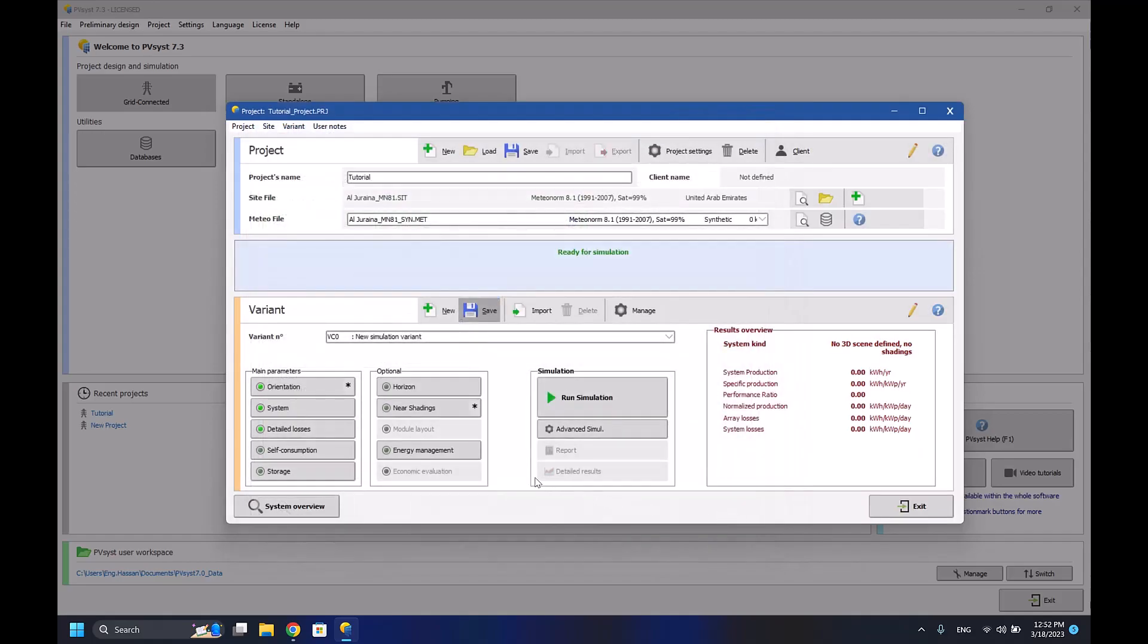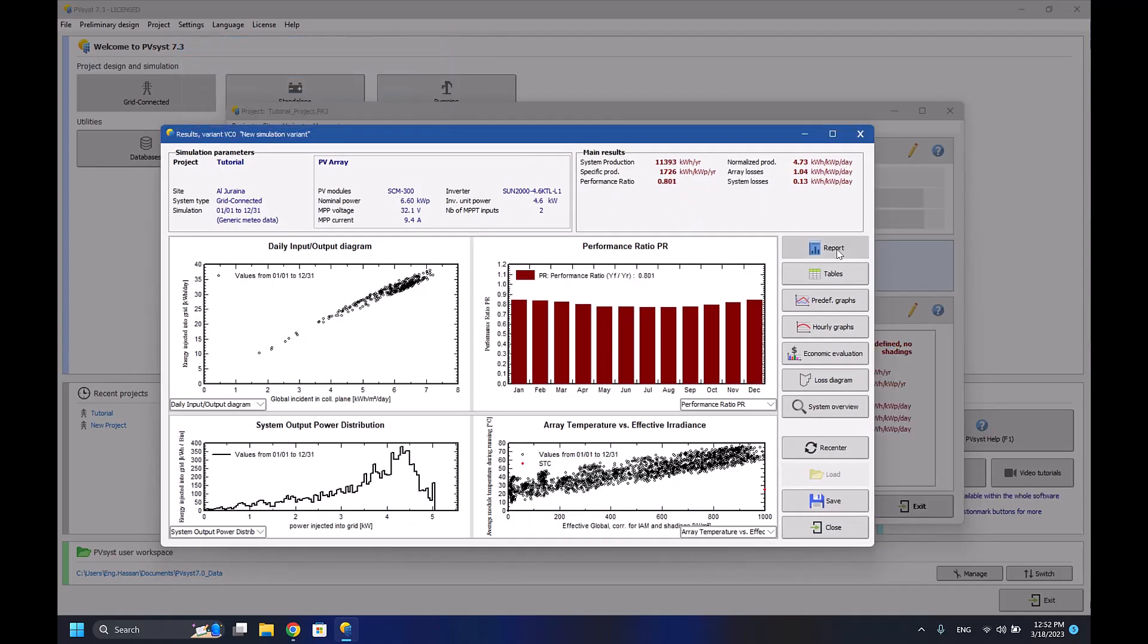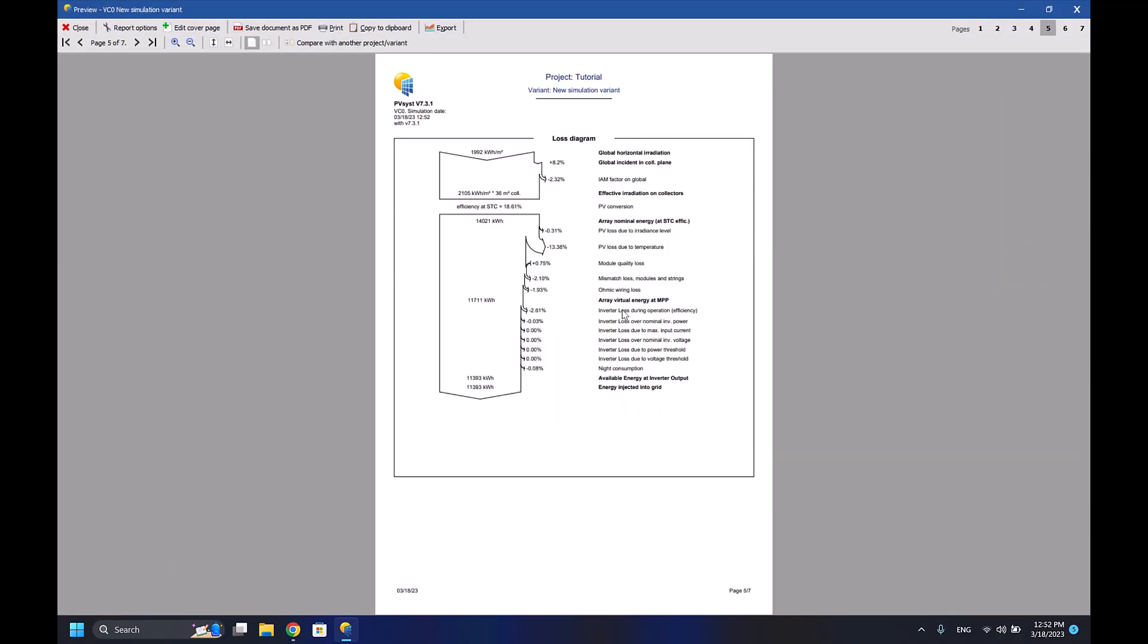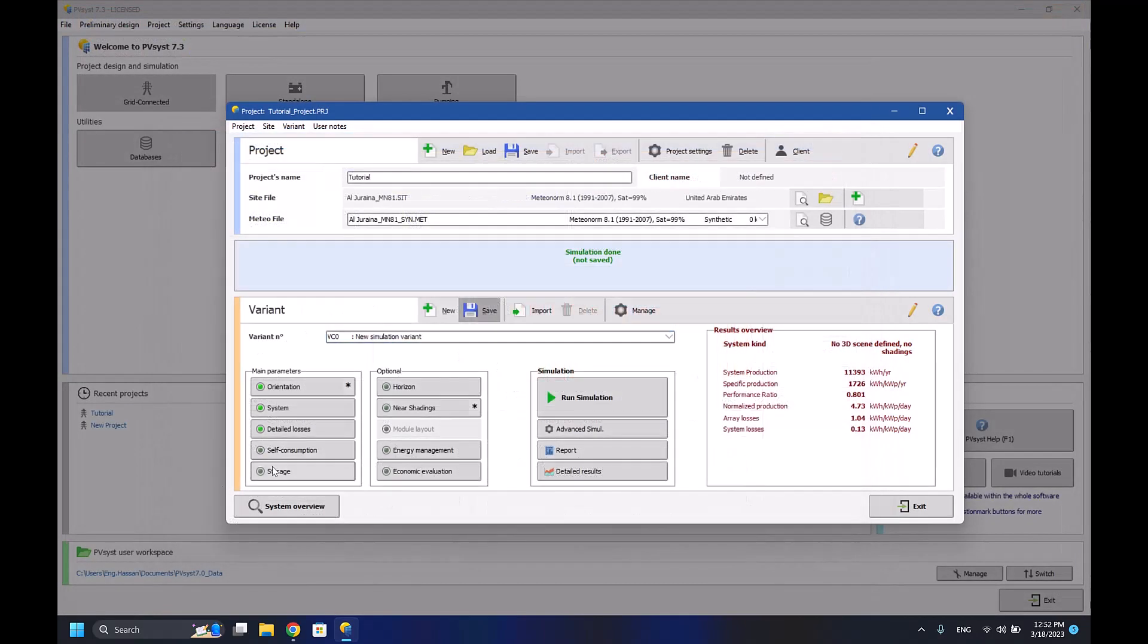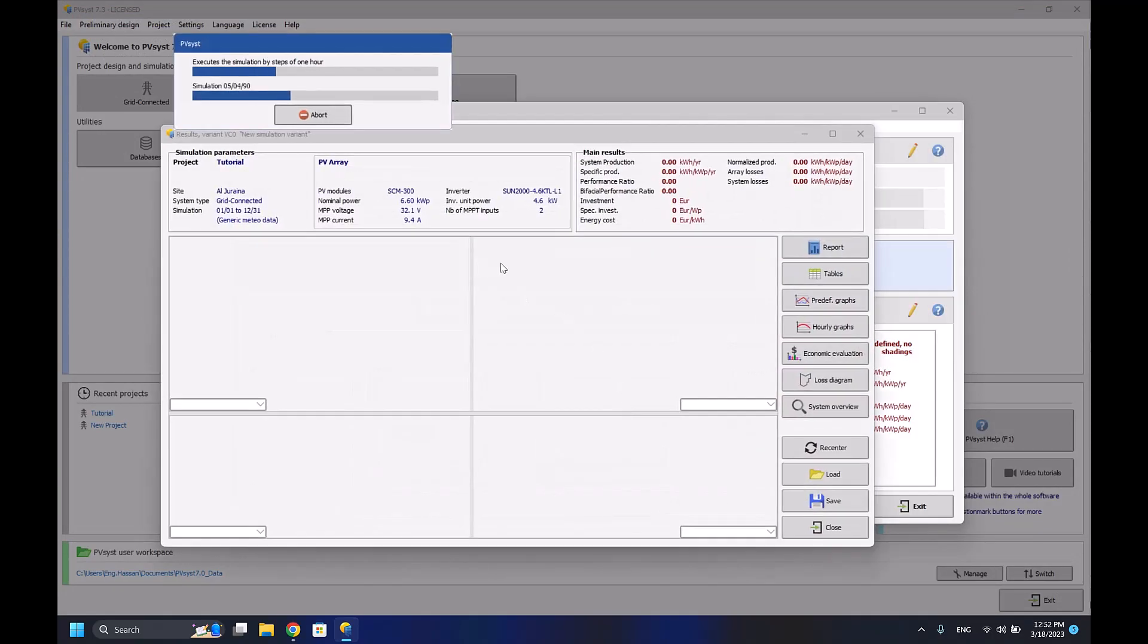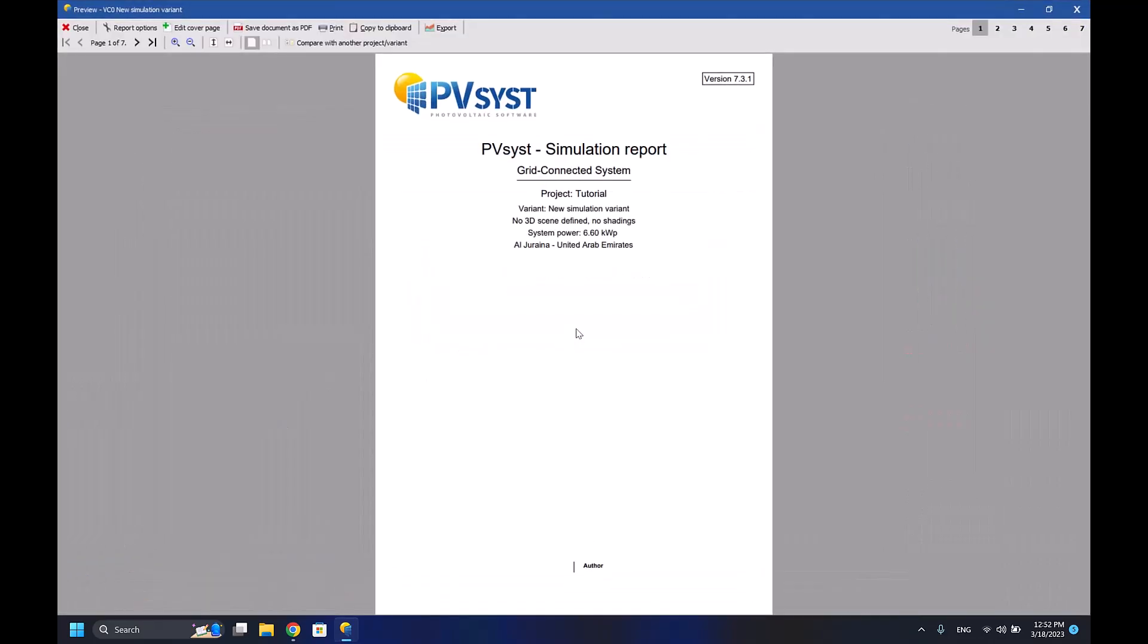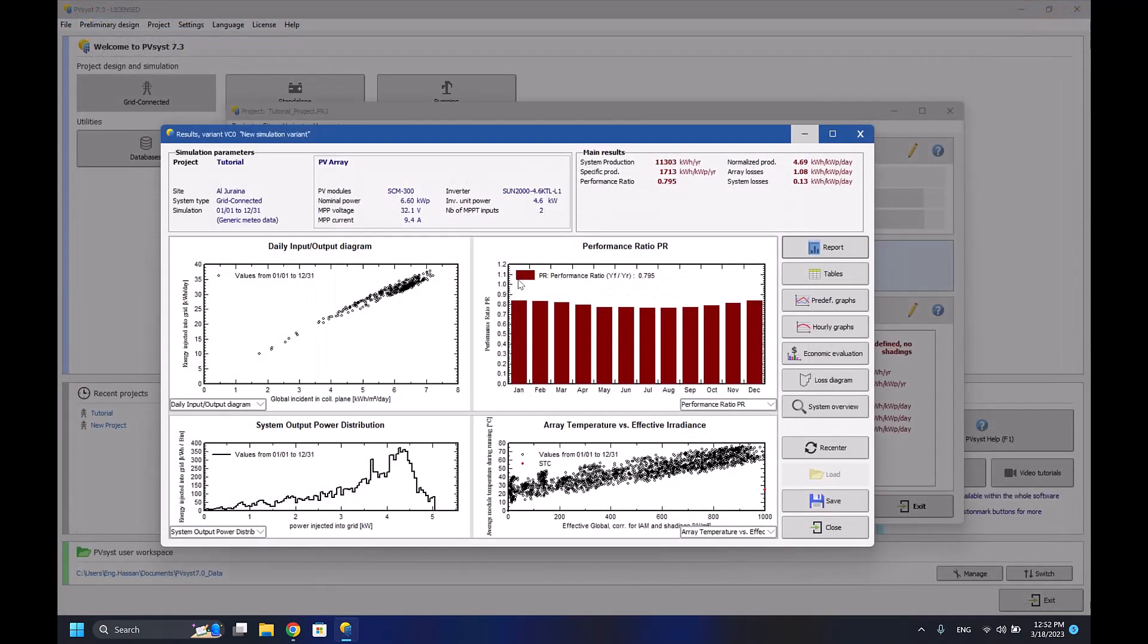Let's press OK and run the simulation again, report the data. As we can see here, the ohmic loss is now 1.93%. So if I increase the ohmic losses even more, for example to 3.5%, the amount of losses I'm losing from the ohmic losses is now 2.71%. So it's really important to have accurate data of the ohmic losses that you have in your system.